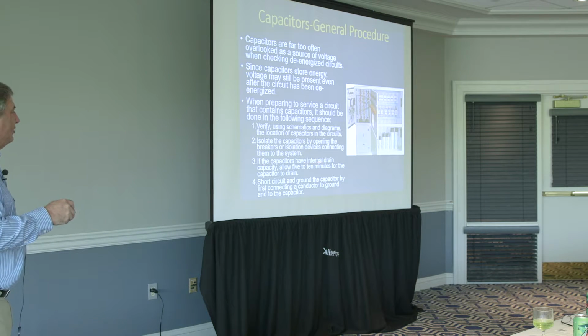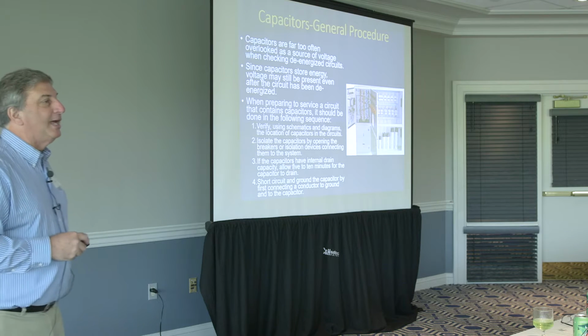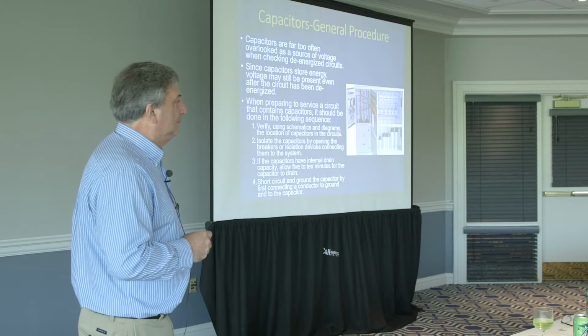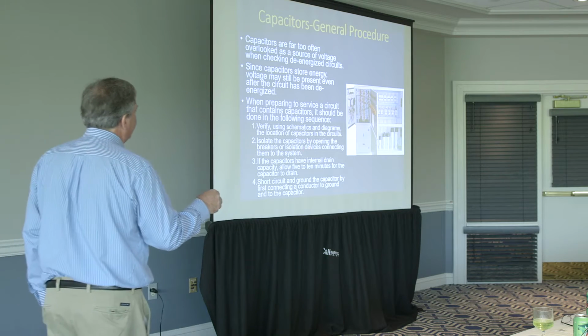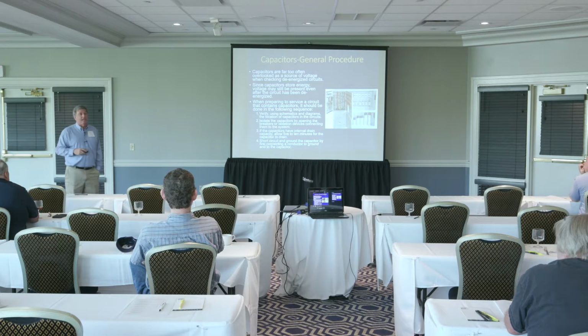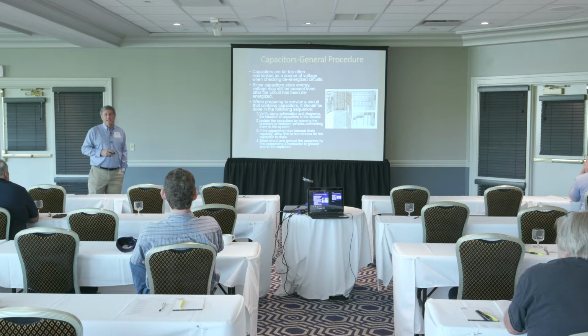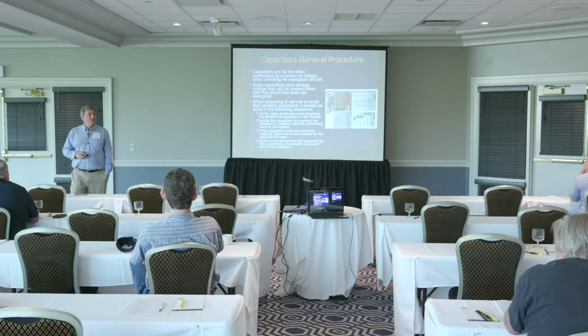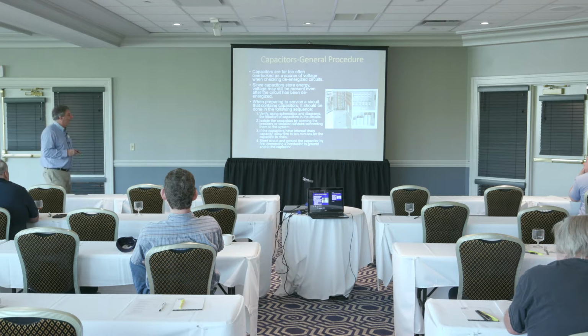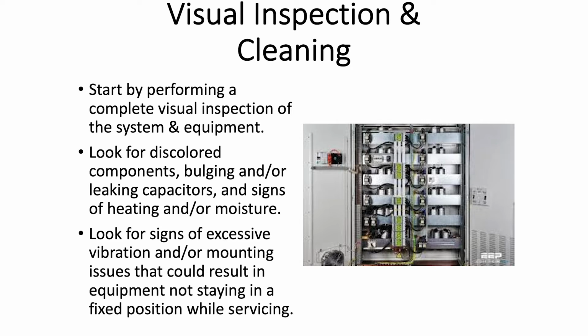Isolate the capacitors. If the caps have internal drains, give them enough time to drain. Most folks will say at least 5, if not 10 minutes, just to be sure. I've seen some where the people were in a hurry, they only gave it a minute and a half, it wasn't fully discharged, problem. Short circuit and ground the capacitor by first connecting a conductor to ground and then to the capacitor. These are all things from power factor correction capacitor manuals from the manufacturers.